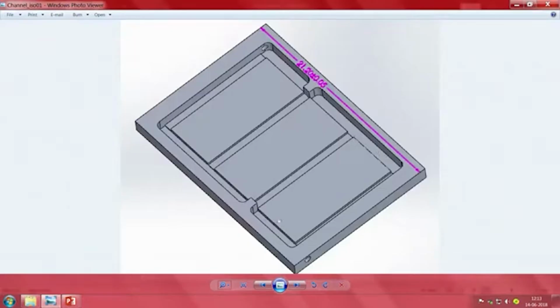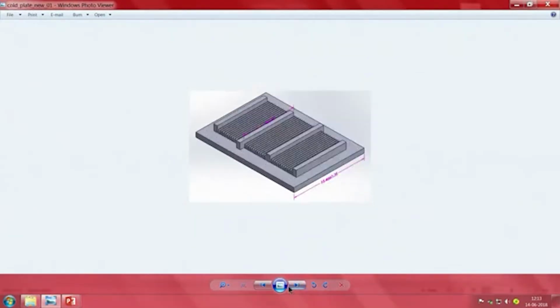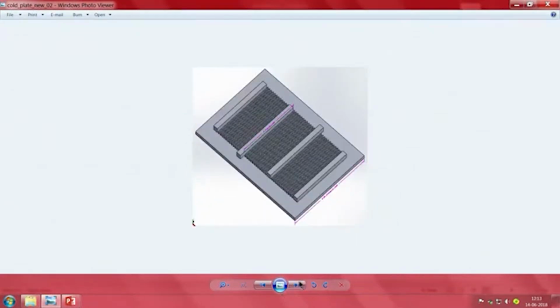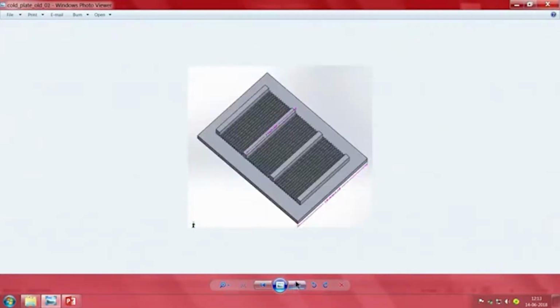Afterwards, since there is a positive pressure, this acts like the next header from here. This part of it is the inlet header, this the outlet header. Next this will become inlet header 2 and this will become the outlet header. And this outlet header again becomes inlet header 3 and then it becomes the outlet header. If you are to make this properly in proper software, you will notice that you can easily carry on simulation work.